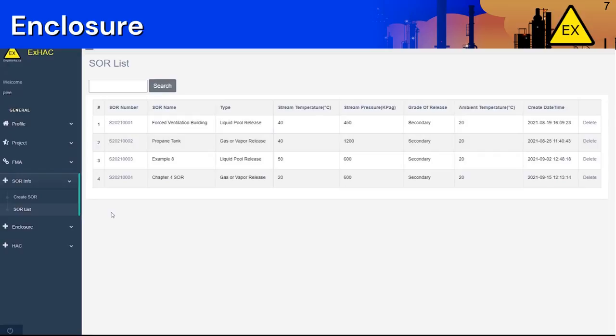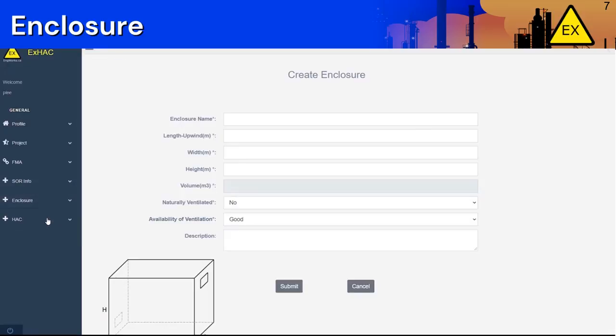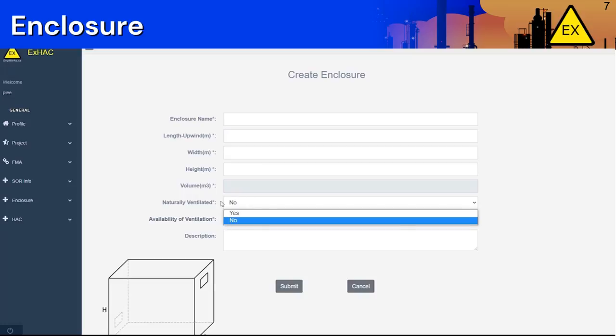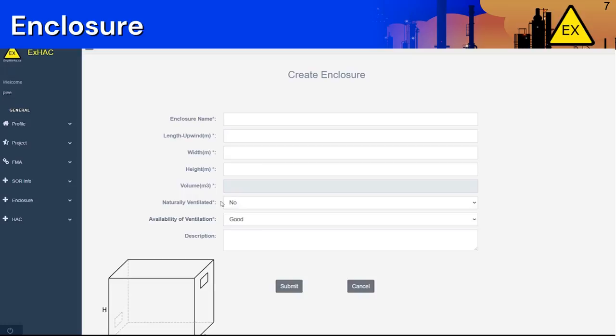The next section is Enclosure. When you click on Create Enclosure, it will take you to a page like this. Here you can name your enclosure and input the required properties such as the width, height, and upwind length. The volume of the enclosure will be calculated automatically. You will also select if the enclosure is naturally ventilated or not. Natural ventilation occurs when wind from the surrounding environment is able to aerate the enclosure interior.